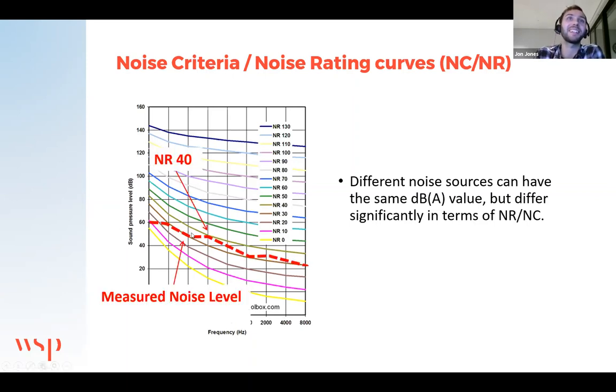Let's take NR40 as the target here. When you take a measurement of a sound, you come up with a spectrum from low to high frequency of what that equipment is, the sound pressure level of that in the room. The way these work then is that the highest point on that pressure level spectrum compared to one of these reference curves is the noise rating or noise criteria curve that it would achieve. So in this example, if we take the red dashed line as a measurement, we'd be achieving NR40 in this space or this example.